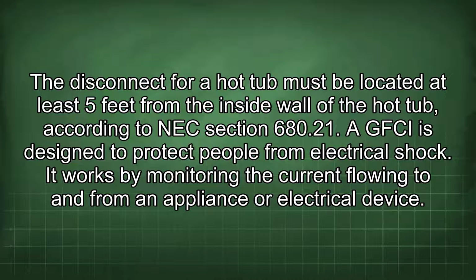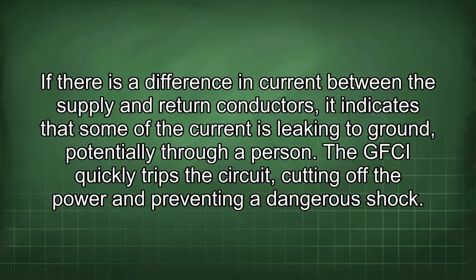A GFCI is designed to protect people from electrical shock. It works by monitoring the current flowing to and from an appliance or electrical device. If there is a difference in current between the supply and return conductors, it indicates that some of the current is leaking to ground, potentially through a person. The GFCI quickly trips the circuit, cutting off the power and preventing a dangerous shock.